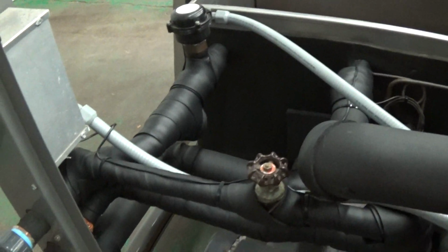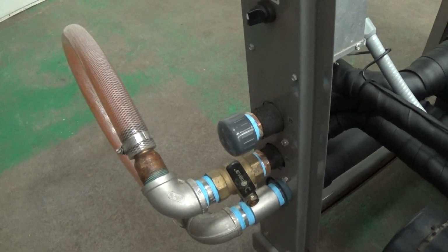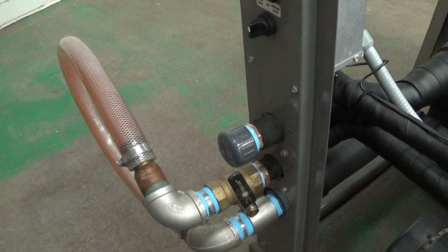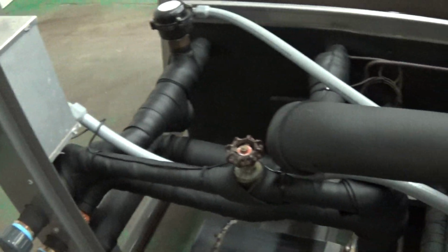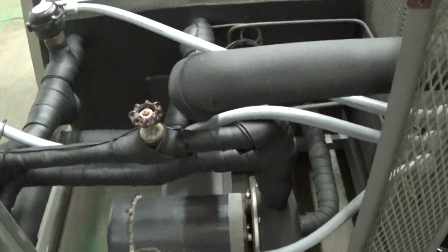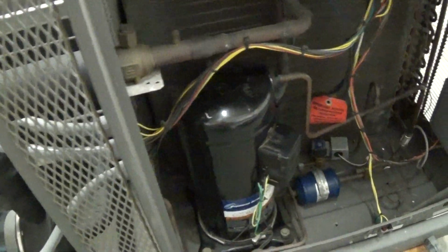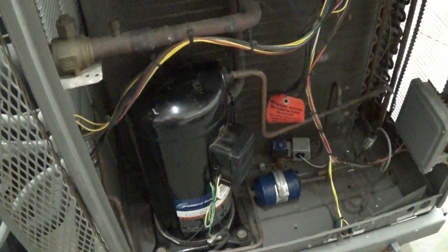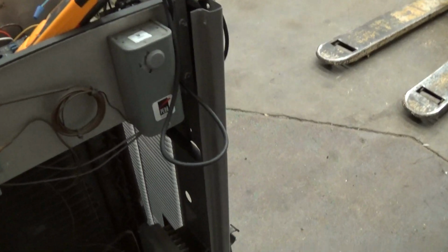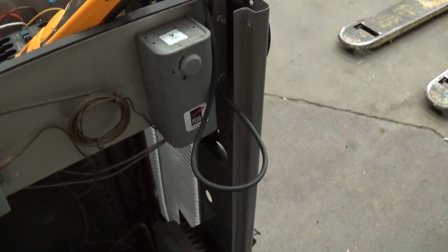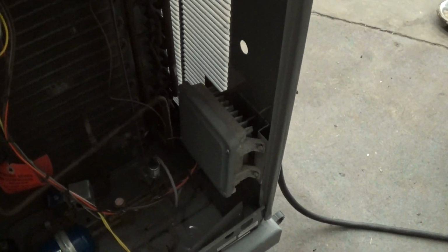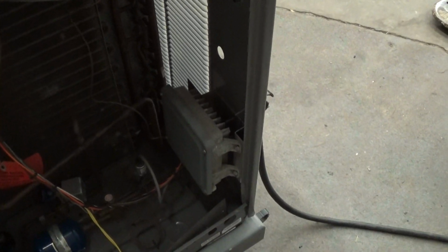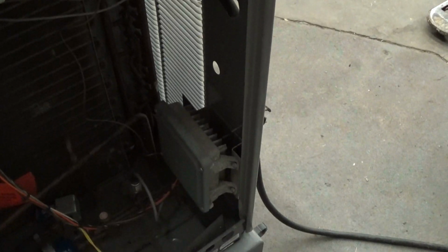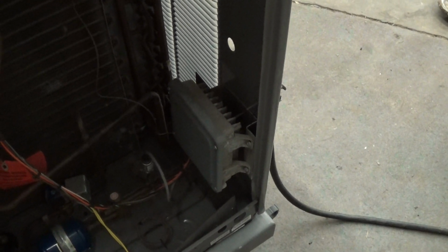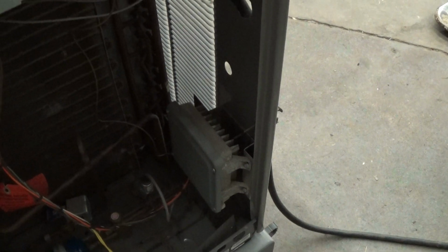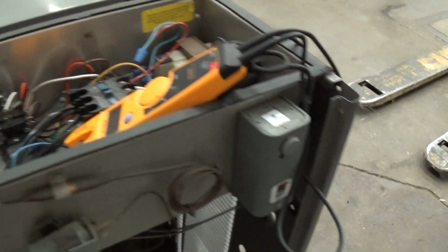At the same time, we need to make sure that there's enough back pressure. Here we just have a loop, but at the same time we have to make sure there's enough back pressure in your glycol loop so that the pump does not overamp. A pump likes to see back pressure and so forth. Some of the other key components we have is the 7.5 horsepower compressor. We have a switch here for low ambient controls that works in conjunction with a fan speed control. So if it's below 0 degrees, this switch activates the P66 fan speed control. If it's above 0 degrees outside, then it's just going to go off fan switching to satisfy the low ambient conditions.